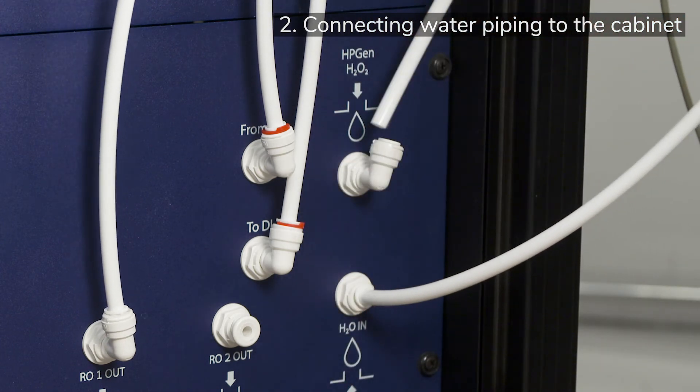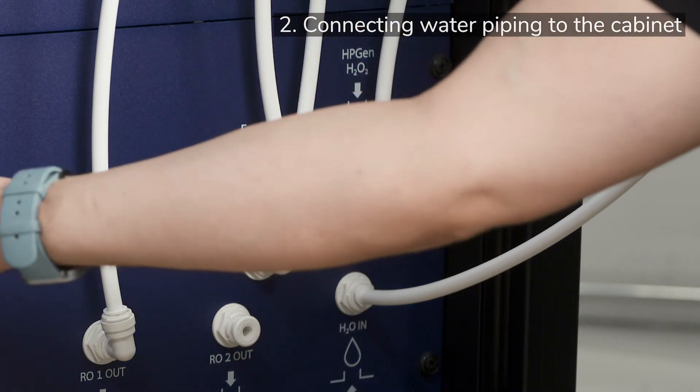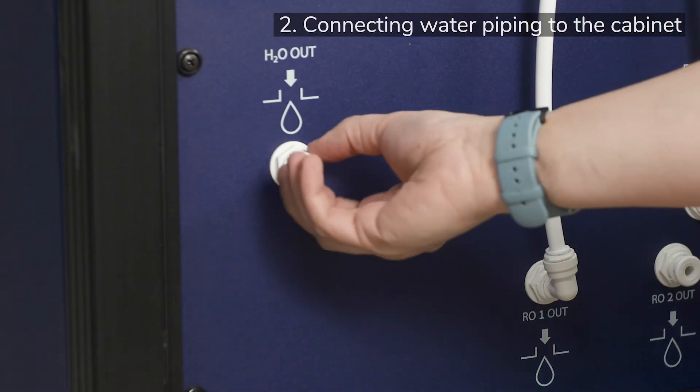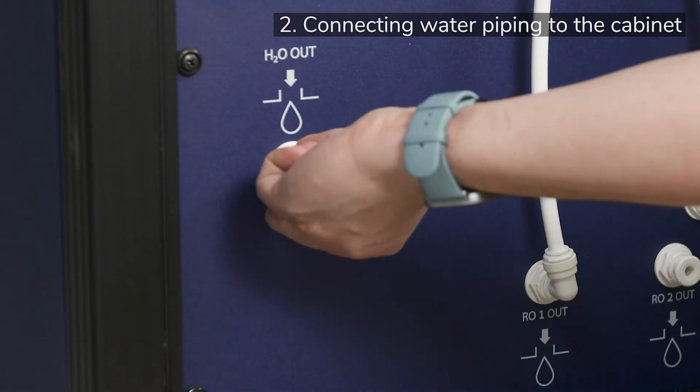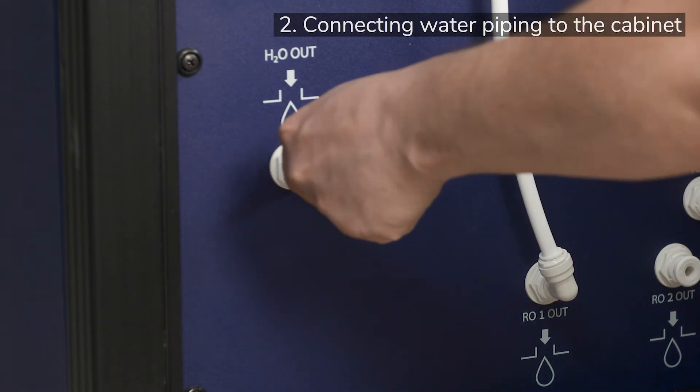Now comes the connection labelled HP Gen H2O2, which is the output peroxide ultrapure solution. This must be connected to the peroxide reservoir that was prepared with fittings earlier in the video. Finally, there is a connection labelled H2O OUT, which is excess water flow from the stack. This should also be connected to the peroxide reservoir.